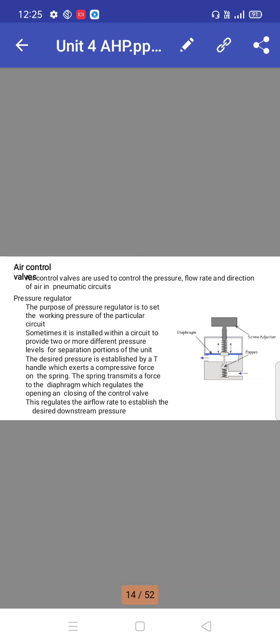The desired pressure is established by a T-handle which exerts a compressive force on the spring. The spring transmits a force to the diaphragm, which regulates the opening and closing of the control valve. This regulates the air flow rate to establish desired downstream pressure.